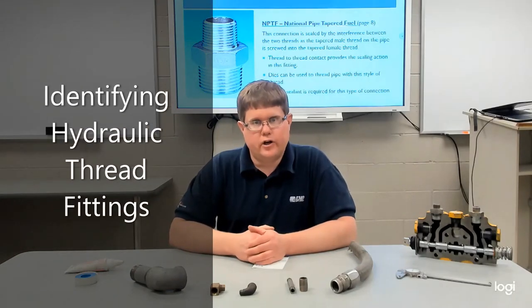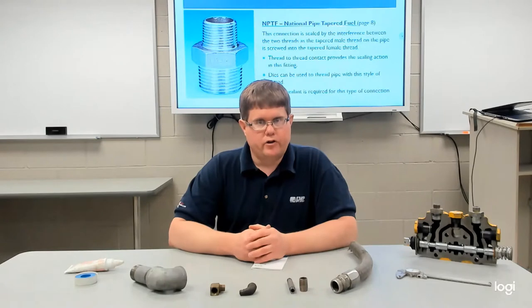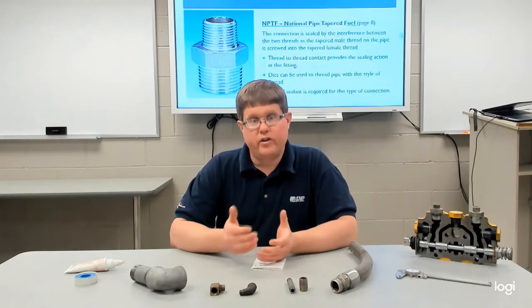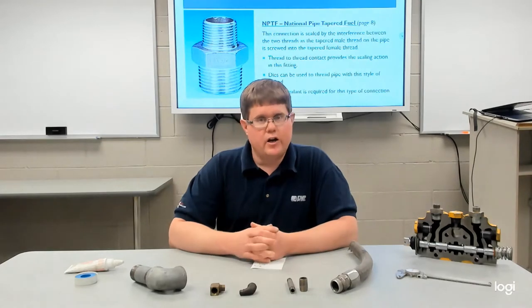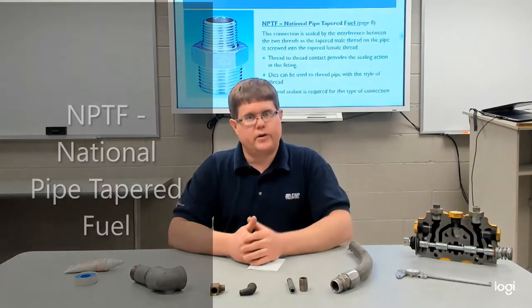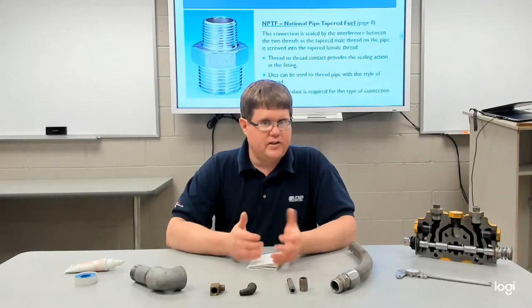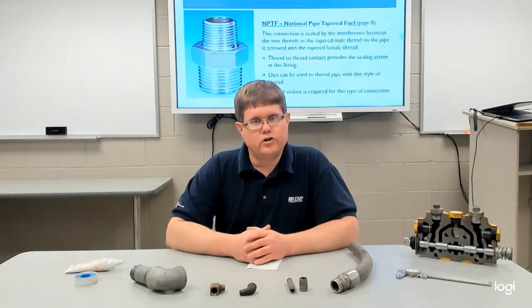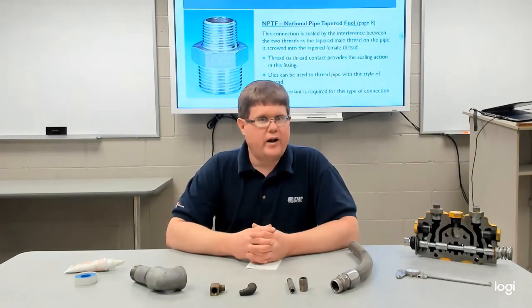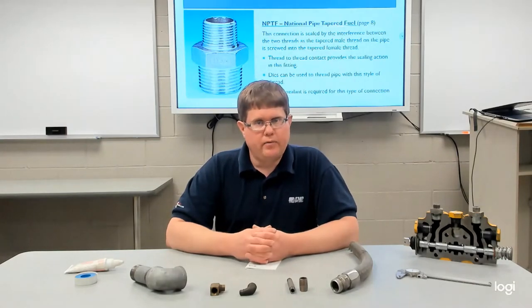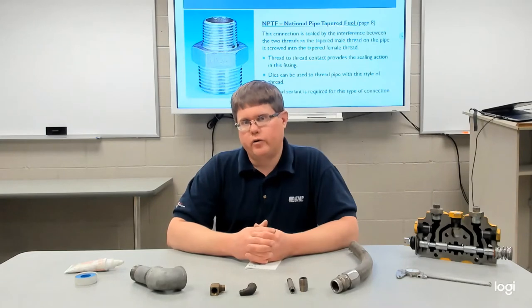Here we're going to take a look at some of the fittings and thread types that are commonly used in hydraulic systems. We'll talk about how to measure and identify them. We'll begin with one of the original sealing types — pipe thread — which is not recommended for use in hydraulics anymore but is still commonly used. NPT (National Pipe Thread) and NPTF (National Pipe Taper Fuel) are slightly different. NPTF has an interference fit designed to provide proper sealing, where NPT does not and will require a sealant.